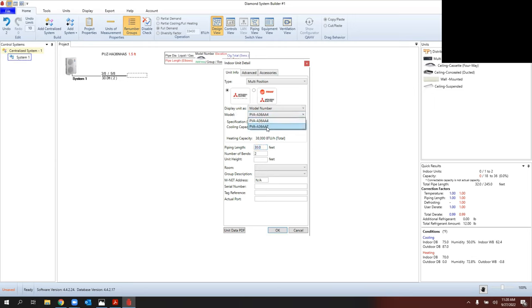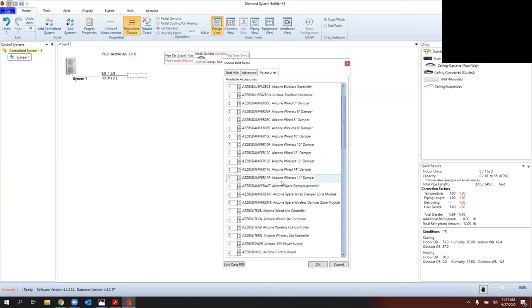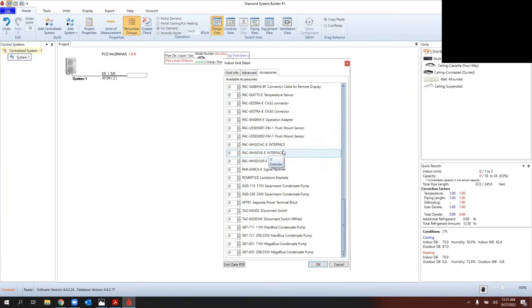The compatible indoor unit auto pre-fills — there are two revisions, so I'll select the dash-seven for the most recent PVA. It auto-fills pipe length and number of bends; I just need to fill in unit height. Let's say this is going into an attic on a two-story home — 20 feet. I can also name the room, which is really important for complex systems with many indoor units. Under Advanced, you can override design temperatures and find all accessories including air zone, condensate pumps, and more.